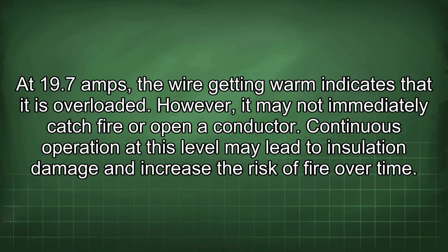At 19.7 amps, the wire getting warm indicates that it is overloaded. However, it may not immediately catch fire or open a conductor. Continuous operation at this level may lead to insulation damage and increase the risk of fire over time.